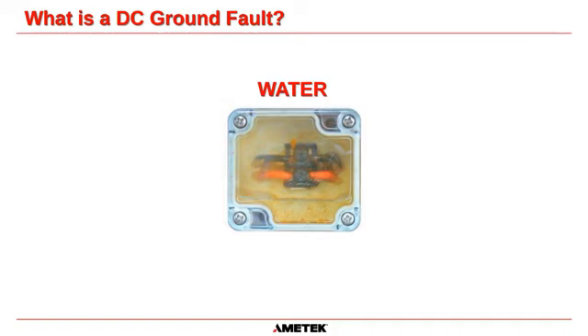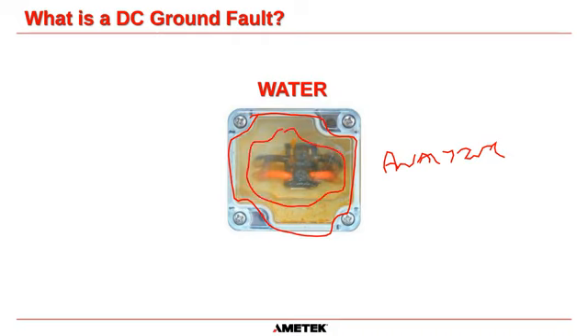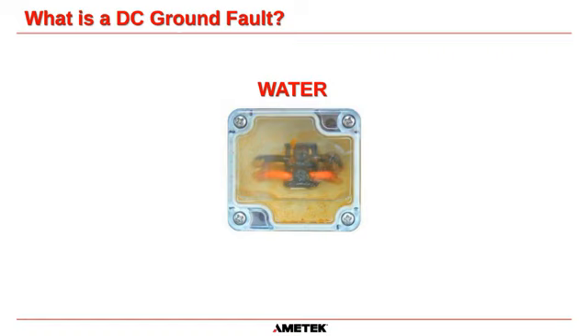Another one is water. This is an external junction box. It's supposed to be sealed. Obviously, this is supposed to be a gasket of some sort. It doesn't have to be a junction box. It could be an analyzer box, anything that is supposed to be outside and sealed from the weather. But if it has a leak or hasn't been screwed down correctly, it can allow water to get in there. And you can see this isn't resin that's in here. This is actually water inside there, and that's going to short out these two cables. And if this was a metal case, it would take one of those conductors down to ground.